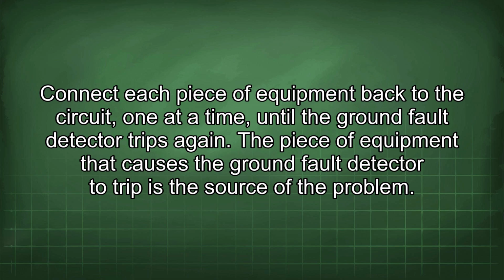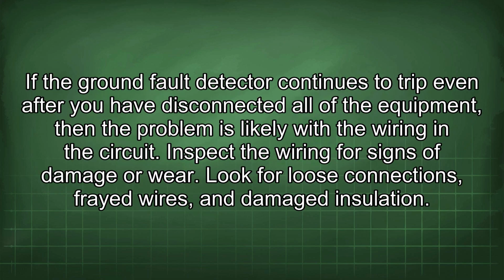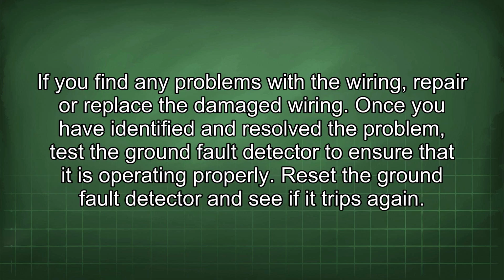The piece of equipment that causes the ground fault detector to trip is the source of the problem. If the ground fault detector continues to trip even after you have disconnected all of the equipment, then the problem is likely with the wiring in the circuit. Inspect the wiring for signs of damage or wear. Look for loose connections, frayed wires, and damaged insulation. If you find any problems with the wiring, repair or replace the damaged wiring.